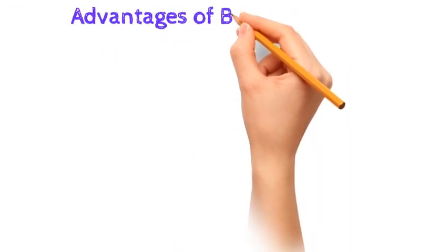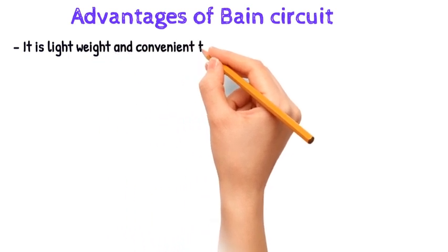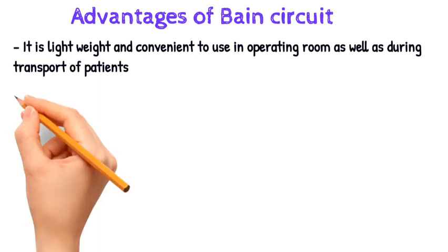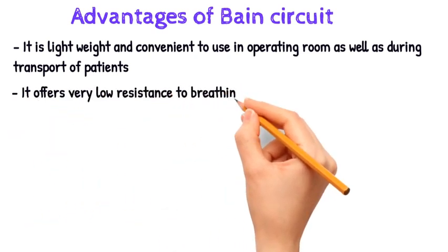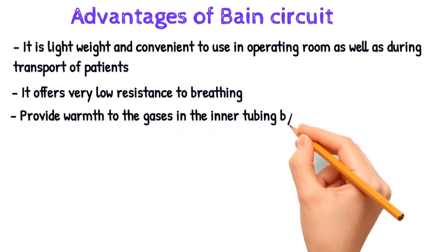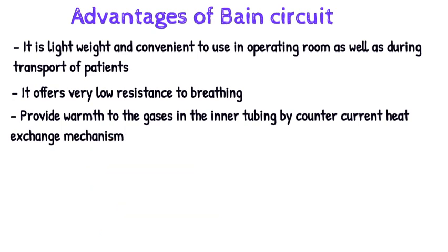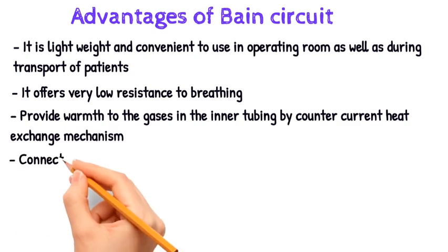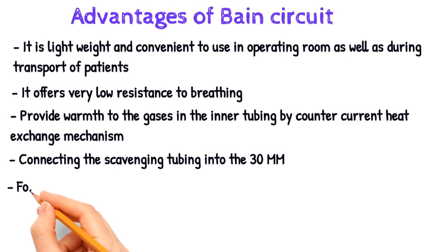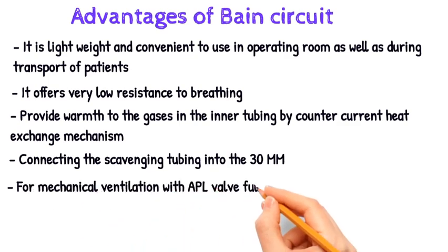Advantages of the Bain circuit: it is lightweight and convenient to use in the operating room as well as during transport of patients. At all fresh gas flows used in clinical practice, it offers very low resistance to breathing. Due to its coaxial structure, exhaled gases in the outer tubing provide warmth to the gases in the inner tubing by a counter-current heat exchange mechanism. Since the APL valve is located far from the patient end, scavenging of exhaled gases is possible by connecting the scavenging tubing to the 30 mm connector at the machine end. Some ventilators can be attached in place of the reservoir bag for mechanical ventilation with the APL valve fully closed.